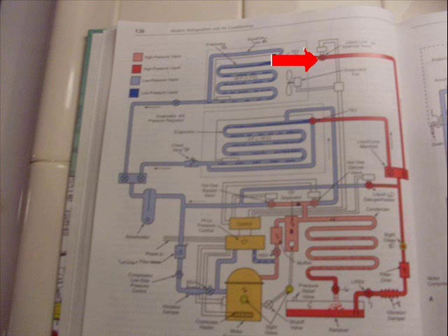And no more refrigerating effect will take place in the high temperature evaporator. Later on, when the box warms up, the thermostat or cold control will energize the solenoid and flow of liquid will then be restored to the TEV and into that evaporator. Liquid line solenoid valve helps control the temperature of the high temperature evaporator by turning on and off the flow of liquid.